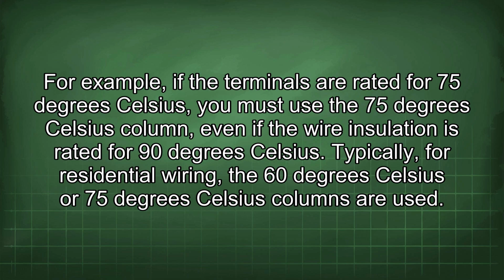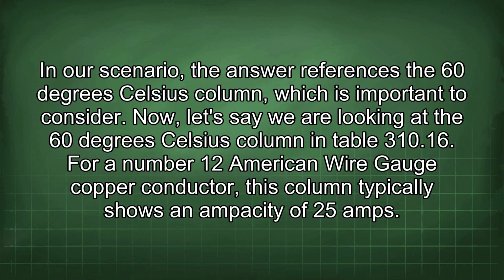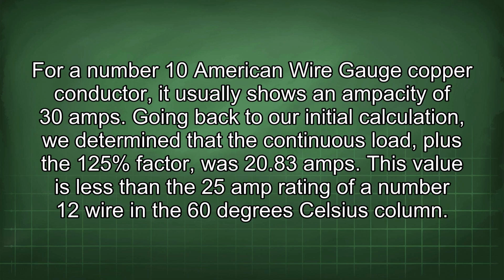Typically, for residential wiring, the 60 degrees Celsius or 75 degrees Celsius columns are used. In our scenario, the answer references the 60 degrees Celsius column, which is important to consider. Now, let's say we are looking at the 60 degrees Celsius column in Table 310.16. For a number 12 American wire gauge copper conductor, this column typically shows an ampacity of 25 amps. For a number 10 American wire gauge copper conductor, it usually shows an ampacity of 30 amps.